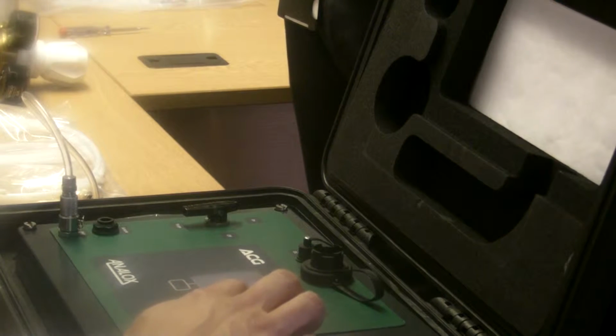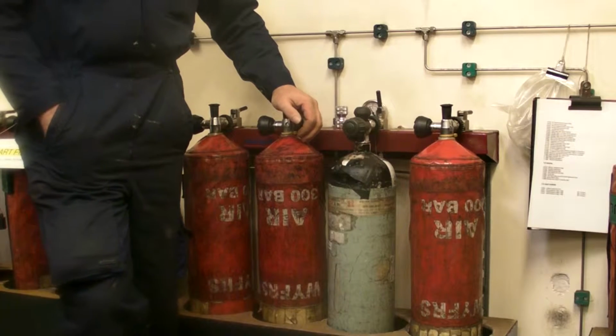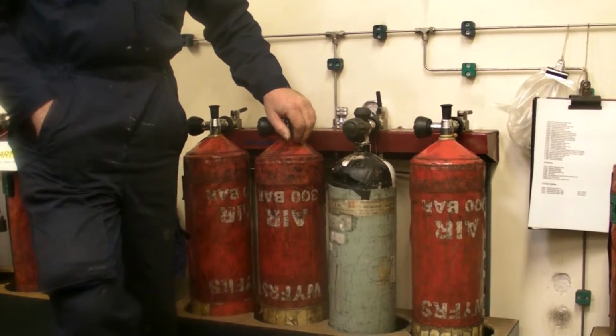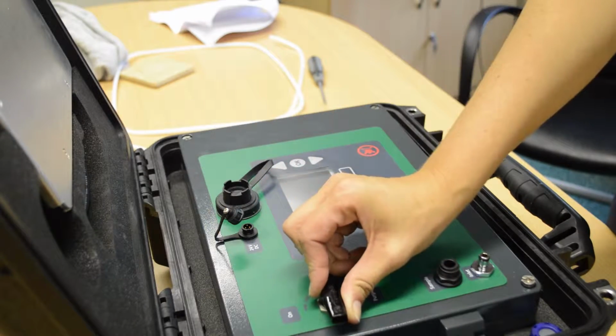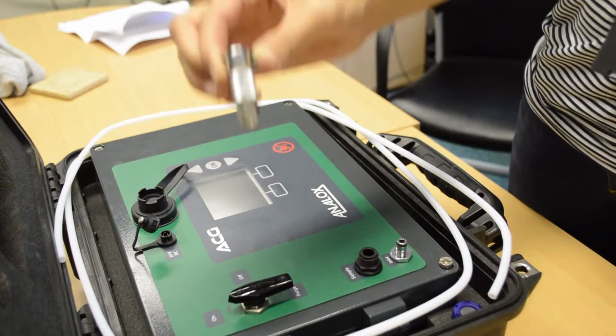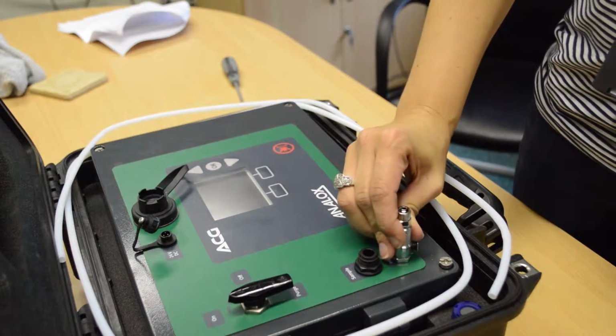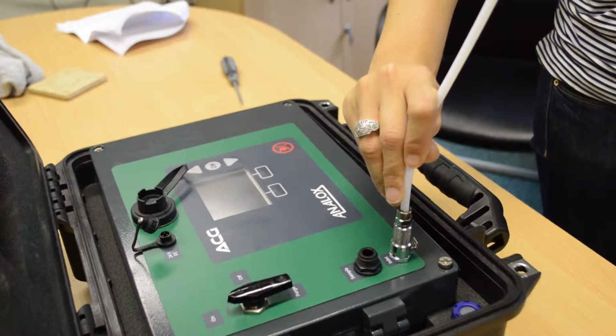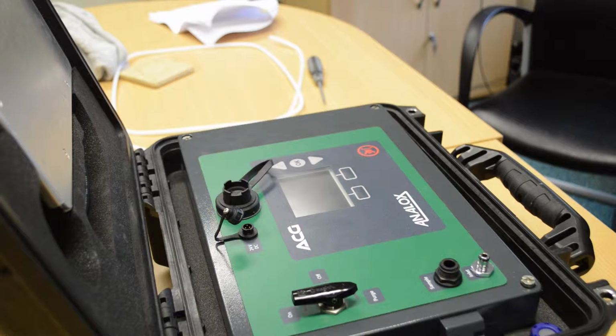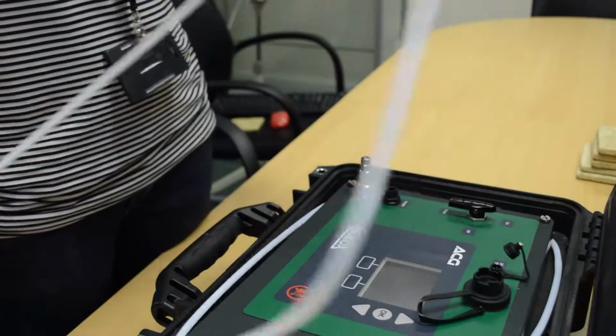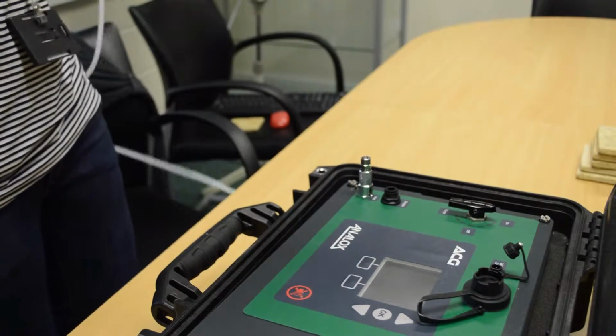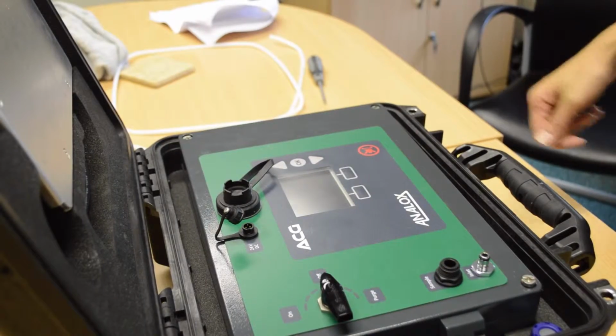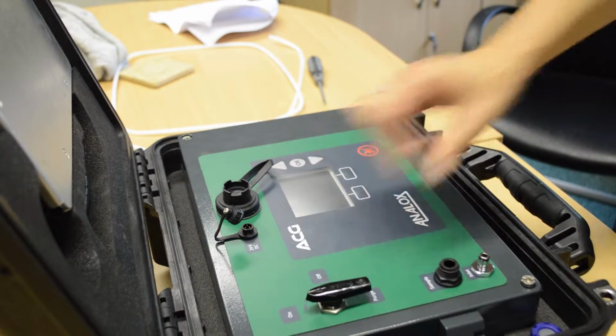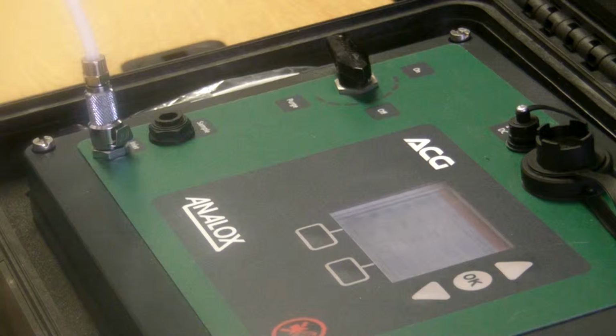Analox recommend that the purge system is used every time the unit is switched on, in case the inlet line has been opened to the atmosphere or it has been exposed to damp gas. Starting with the valve in the off position, apply pressure to the inlet between 5 and 10 bar gauge, using the supplied LinkTech inlet calibration connector. Once pressure is applied, the valve should be turned to purge and left for 2 minutes, using the supplied 2 metre PTFE pipe so that the pipework prior to the ACG Plus can be purged of any stale or damp gas and any moisture on the pipe walls can be dried out. Once the purge is completed, the valve can be turned to the on position to allow the sensors to start analysing the gas sample. This process will ensure the ACG Plus sensors can stabilise as quickly as possible to the gas you wish to measure.